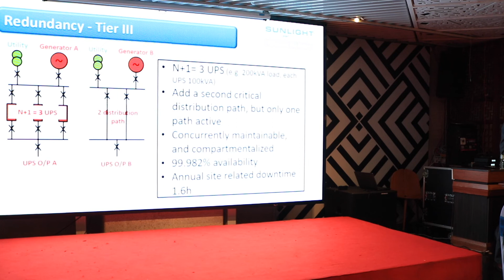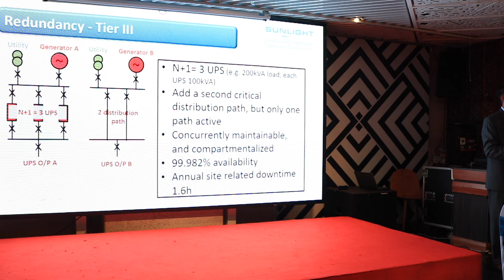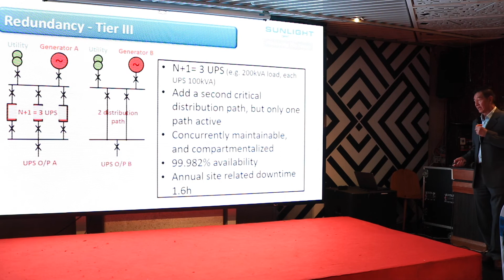So just now, for the power calculation, I explained that you take the nameplate of all the equipment, you must add your redundancy. That's where it comes in. Your redundancy adds to those losses, and of course to the cost of the investment, and of course to the space. But it now improves your availability to 99.982%. Your downtime cuts down to below 2 hours. Service level agreement is very important for this sort of level of data center. You insist that anytime your call comes, whatever equipment supply will be there within 2 hours.